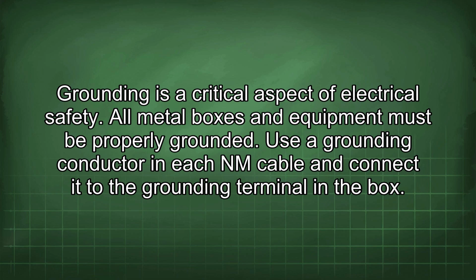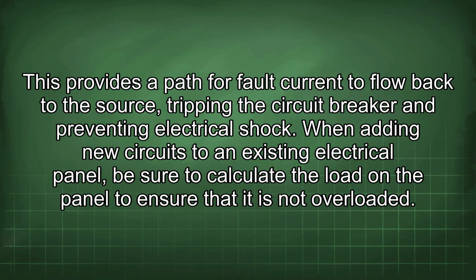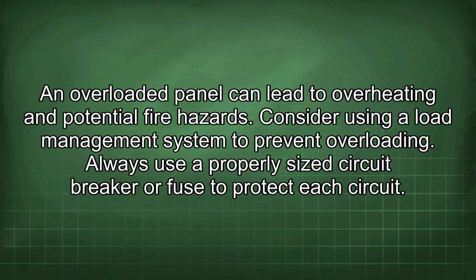Grounding is a critical aspect of electrical safety. All metal boxes and equipment must be properly grounded. Use a grounding conductor in each NM cable and connect it to the grounding terminal in the box. This provides a path for fault current to flow back to the source, tripping the circuit breaker and preventing electrical shock. When adding new circuits to an existing electrical panel, be sure to calculate the load in the panel to ensure that it is not overloaded. An overloaded panel can lead to overheating and potential fire hazards.